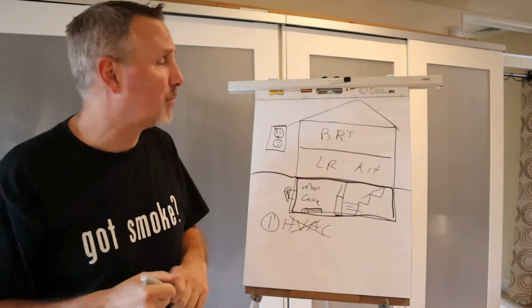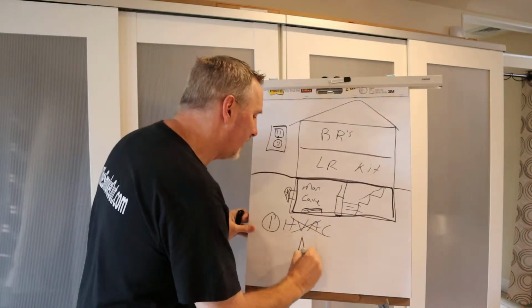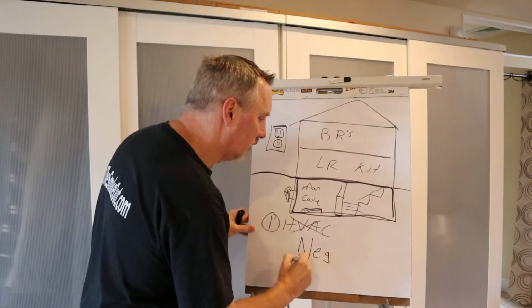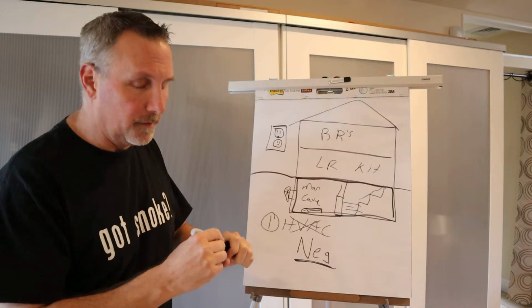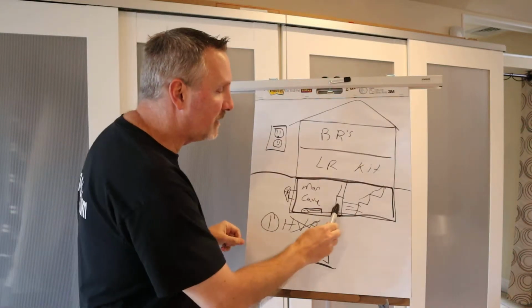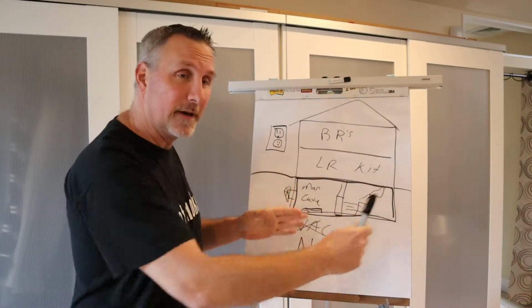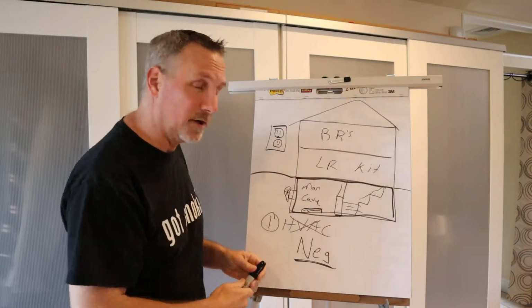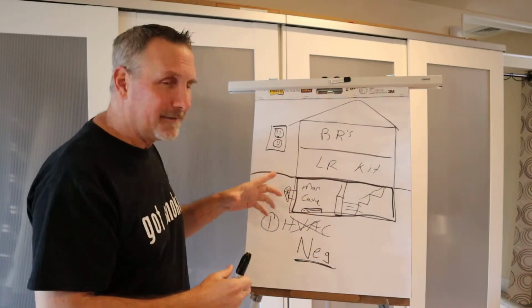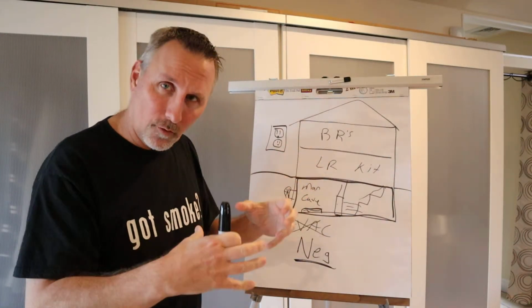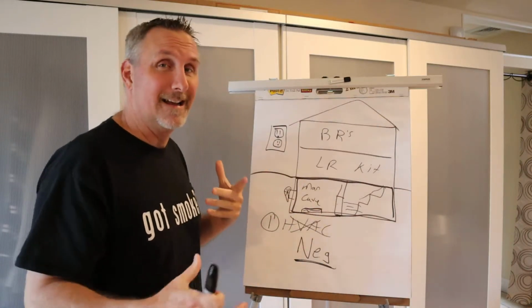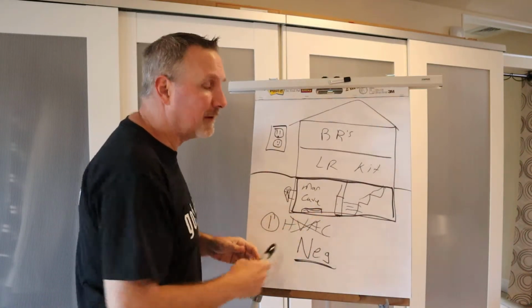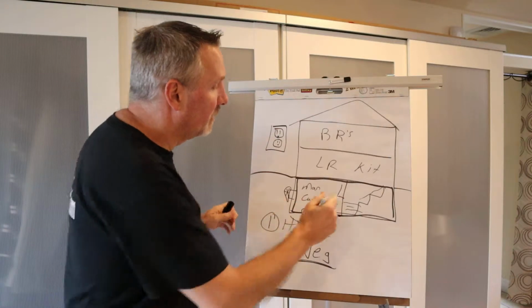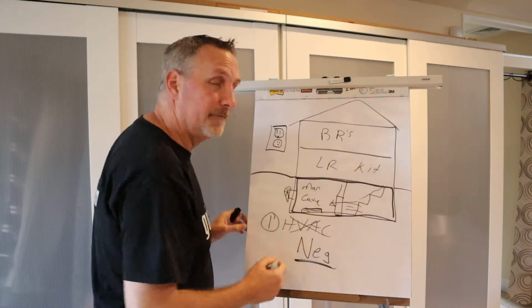A slight amount of exhaust pulling air out of the man cave and throwing it outside creates what I call negative pressure. That's critical because anytime the doorway opens to the adjoining space, if you've got negative pressure, this exhaust is creating almost like a vacuum in the room. It's exhausting air, there's not much coming in. When you open the door, that air is going to come into the room.